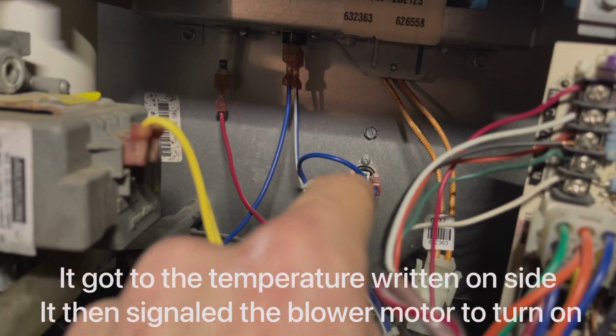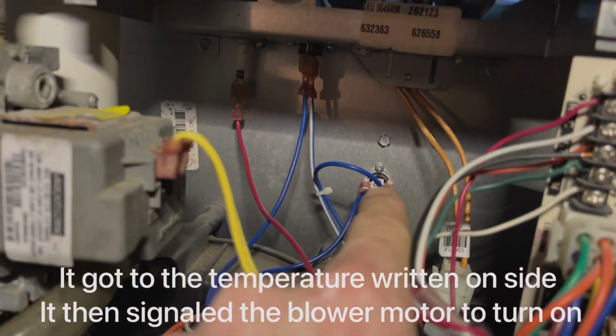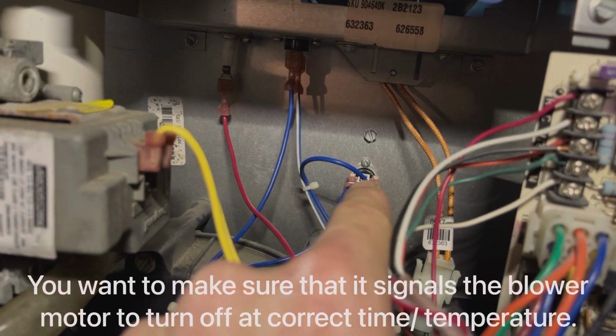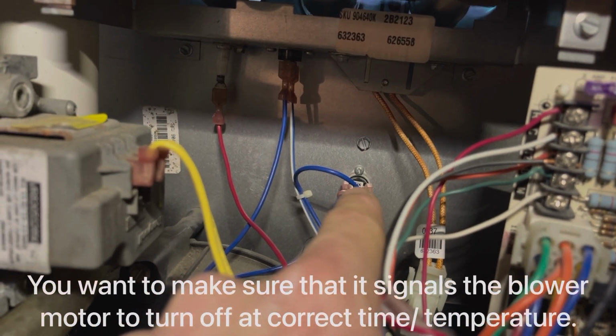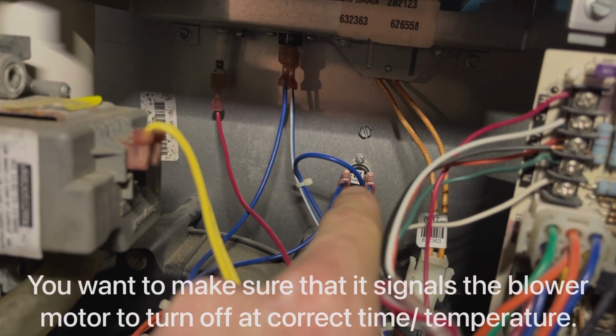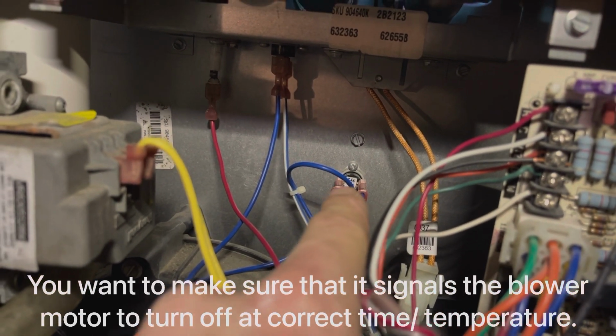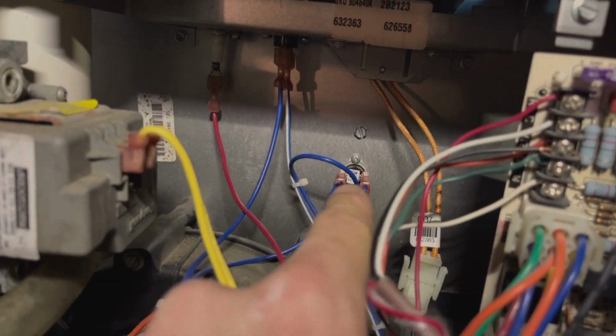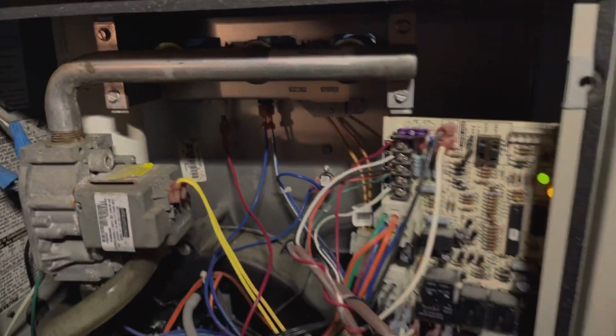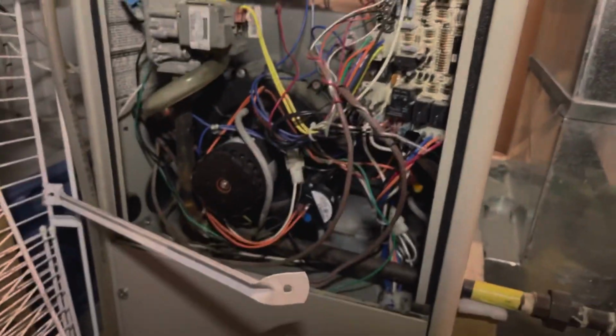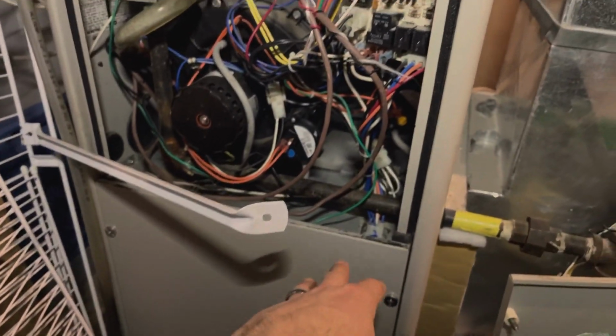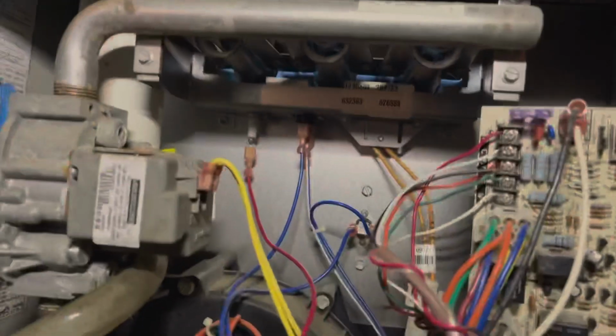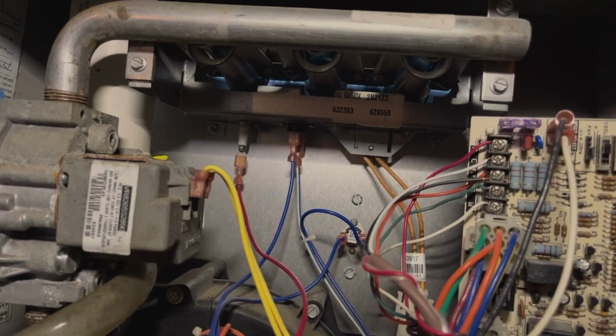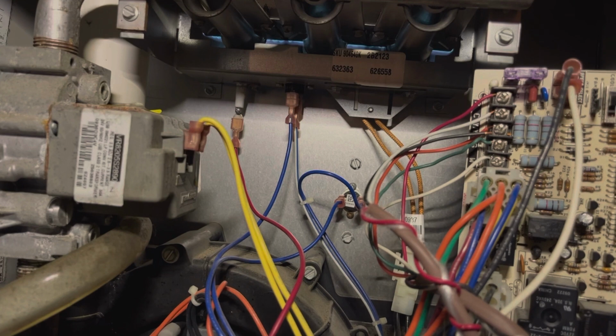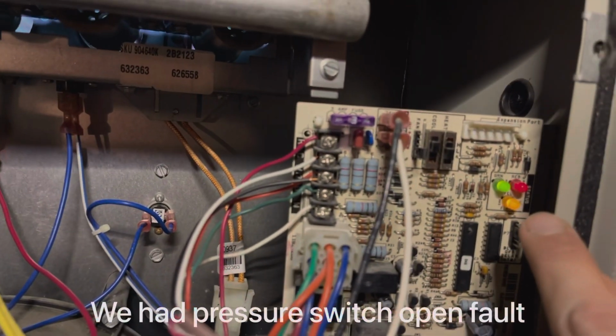Well, not necessarily, but it turned it on, so it's functioning. It could have another issue down the line where it doesn't trip it off or whatever, but likely this is working. It got to the right temperature, sensed the temperature building up below the heat exchanger, and kicked on the blower motor, which also means your blower motor solenoid worked to turn on the blower motor, and that is functioning. Now, this could run for a bit, and we've had an issue before where it ran for a bit, and then we had an issue with lights flashing.